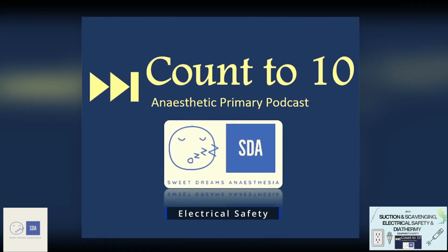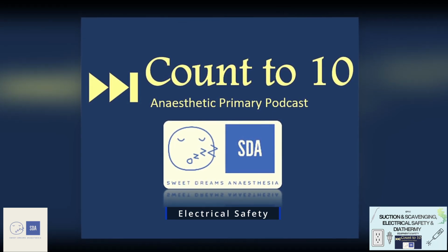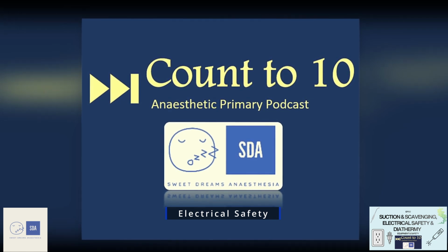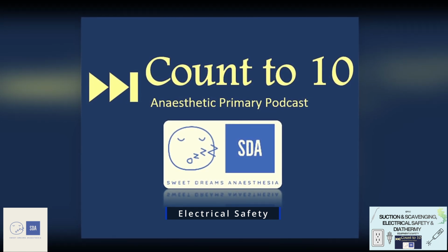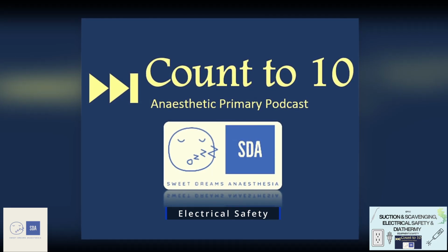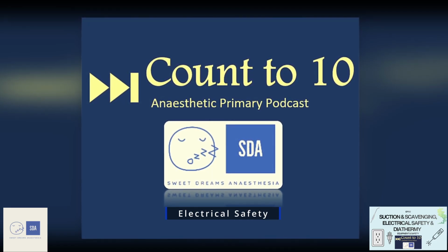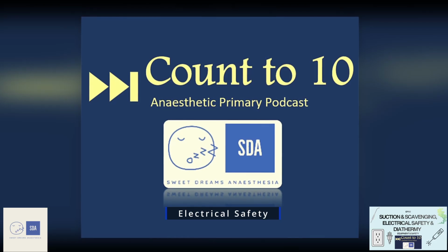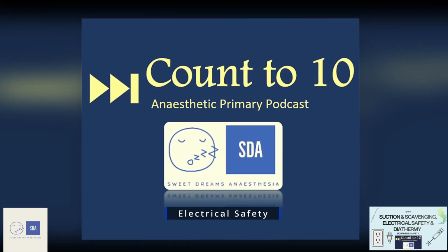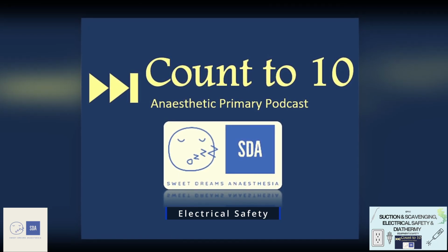You need a neutral wire which carries the electricity back from the device to the power source. And then the earth wire, its main function is a safety feature. Its role is to strictly protect the device. It provides the path of least resistance for electricity to flow if there's a leakage within the circuit.